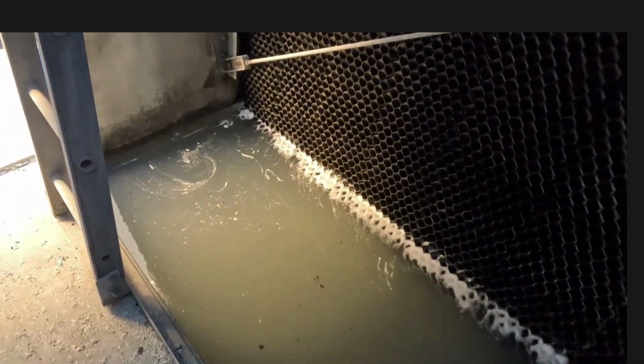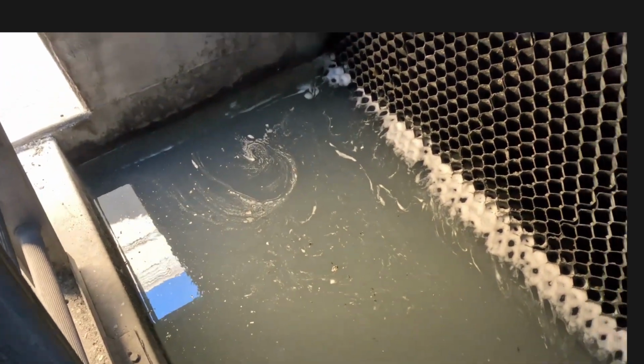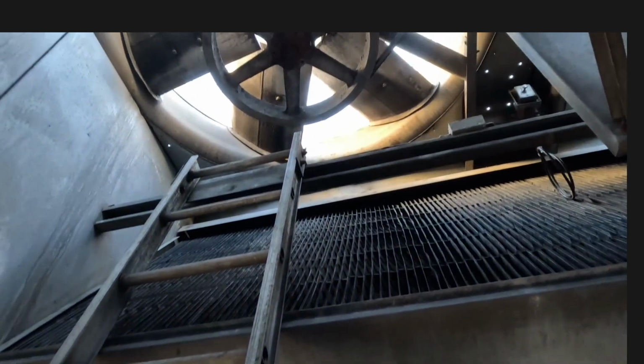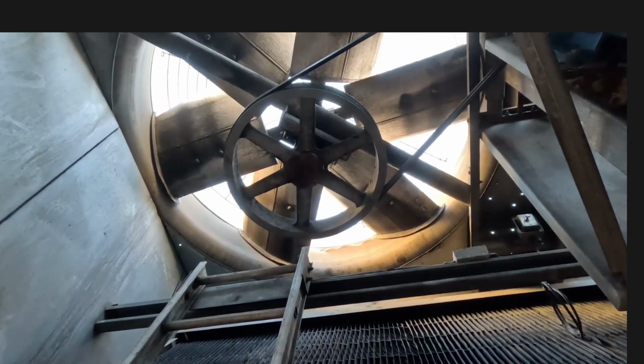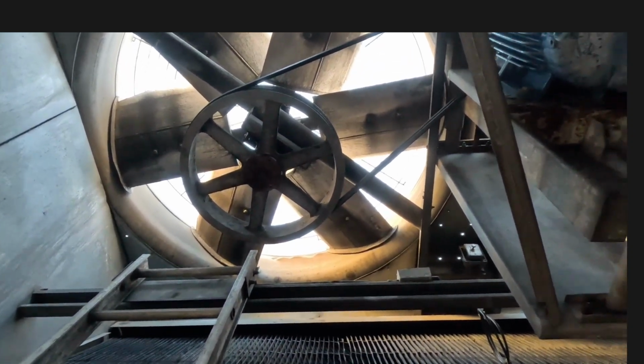Floor's a little dirty, needs some cleaning. See a little foam down there with the water and such. Yeah, water's not looking too good. So it looks like this tower needs some flush and a cleaning, basically with the power washer as well. The fill inside is not too bad from the inside, but I'll show you guys a view from the outside of this fill. In any case, what I really wanted to concentrate on is going up those ladders and checking the pulleys, the fan pulleys for this tower.